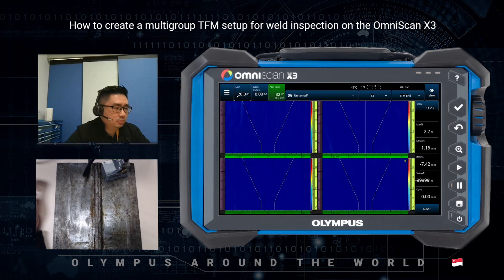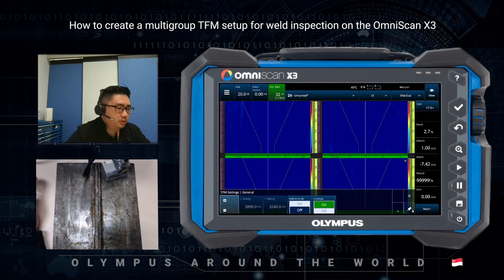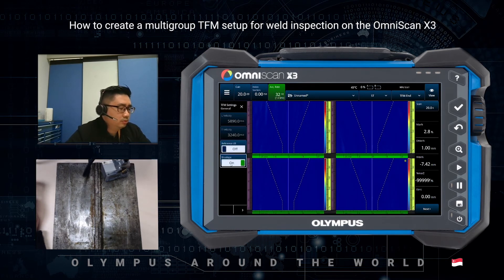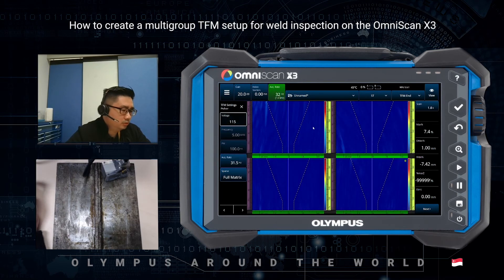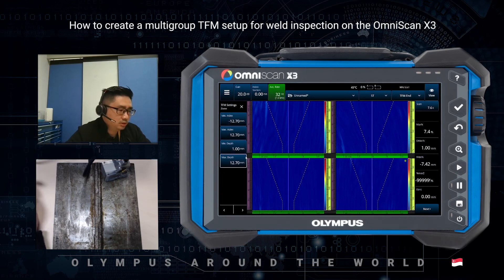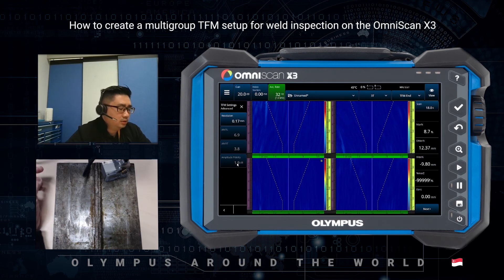Now we do some fine tuning. Go to TFM settings — General — and pin this panel to the side. Envelope is on, great. For voltage, let's set high voltage at 115V — this is global for all groups. The TFM zone settings are exactly as we defined earlier, and you can modify them. The resolution is 0.17 for all four groups, and the amplitude fidelity is 1.9 dB, which is below the required 2 dB threshold.